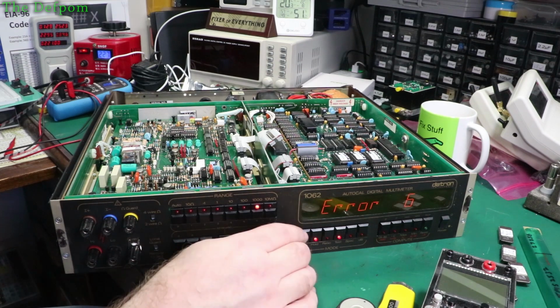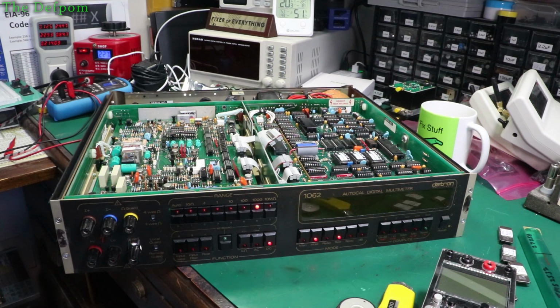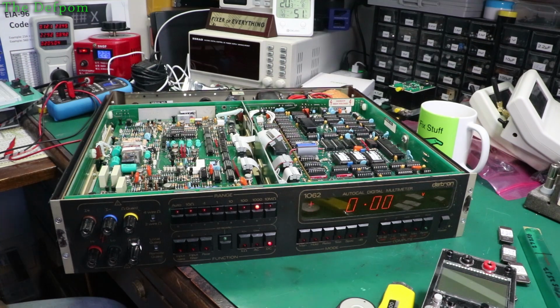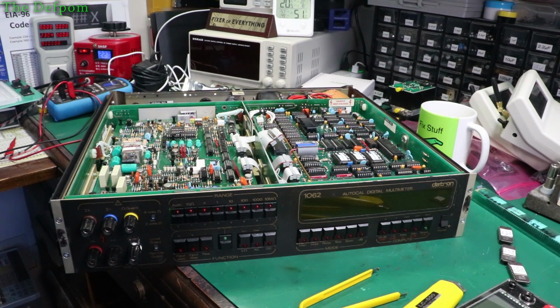Still there, okay, right. So yes, I've got an issue with this still in the ohms range. That's fine, at least I know what I'm dealing with. I thought I'd fixed all the problems, but apparently not. Reading the manual about self-test failure, it measures a 10 kilo ohm range and links a resistor across the I positive and I negative terminals, and it measures that resistor voltage with the DC side in order to verify it's working.